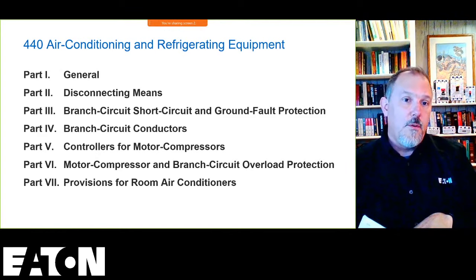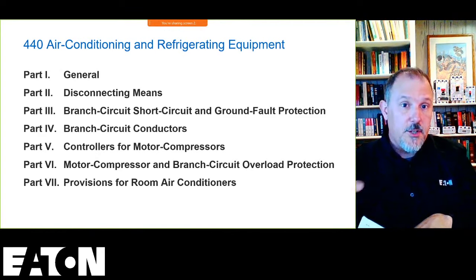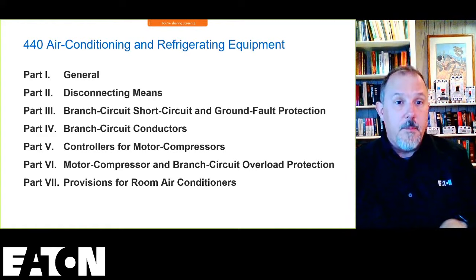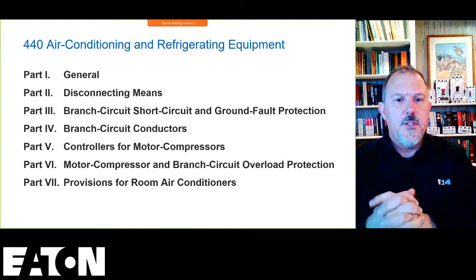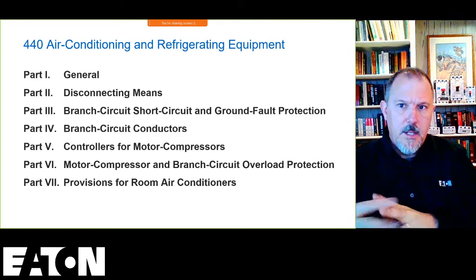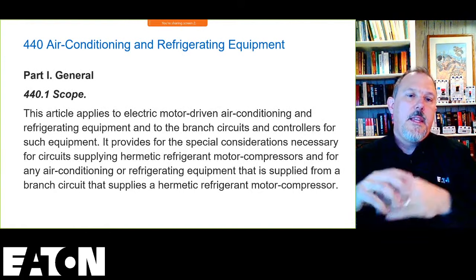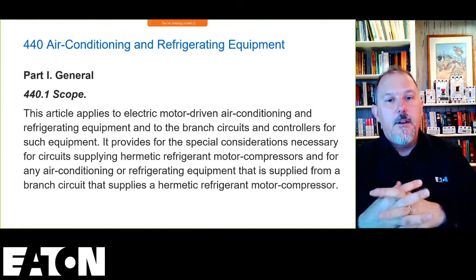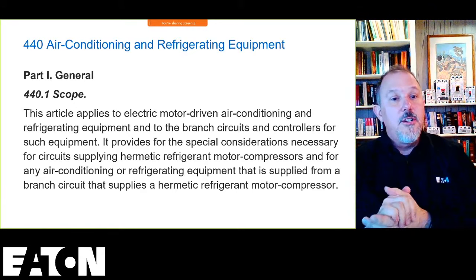We go back to Article 440 and we look at Part 3, which is your branch circuit, short circuit, and ground fault protection. And we look at Part 6 for motor, compressor, and branch circuit overload protection. Now, if I go back to 440, this tells me that the article applies to electric motor-driven air conditioning and refrigeration equipment, and to the branch circuits and controllers for such equipment.